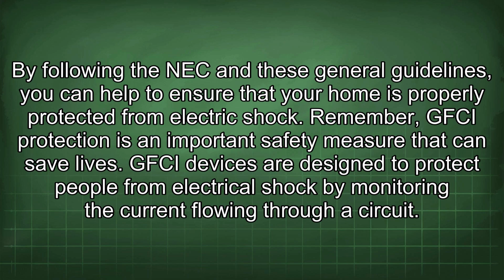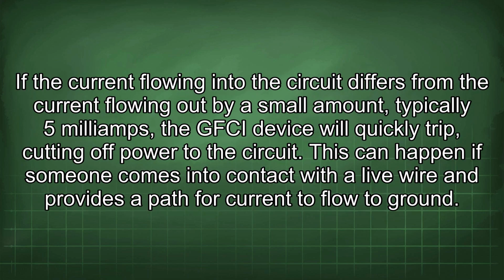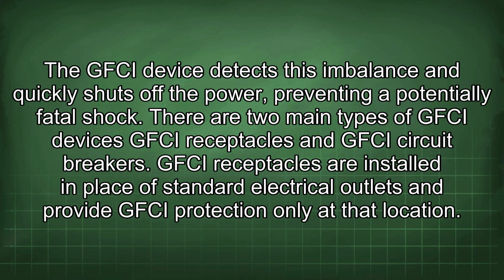GFCI devices are designed to protect people from electrical shock by monitoring the current flowing through a circuit. If the current flowing into the circuit differs from the current flowing out by a small amount, typically 5 mA, the GFCI device will quickly trip, cutting off power to the circuit. This can happen if someone comes into contact with a live wire and provides a path for current to flow to ground. The GFCI device detects this imbalance and quickly shuts off the power, preventing a potentially fatal shock.